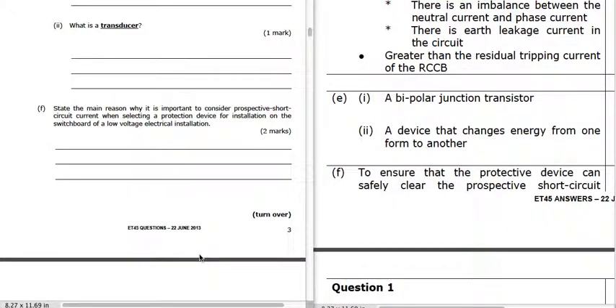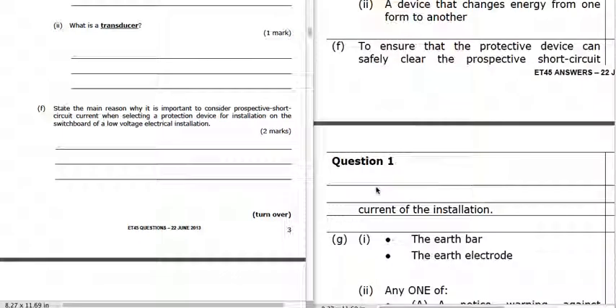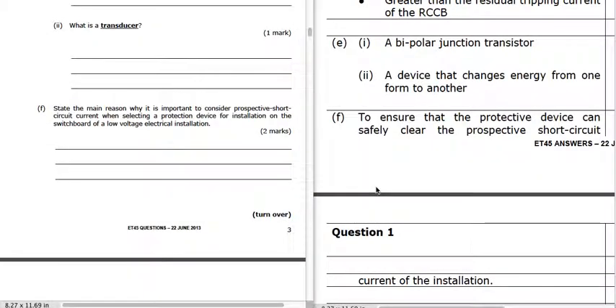The main reason why it's important to consider prospective short-circuit current when selecting a protective device: the prospective short-circuit current is the maximum current that will flow in the system under a fault condition. The protective device we put in there needs to be able to clear a fault current of that value, so its rating must be higher than that prospective short-circuit current.